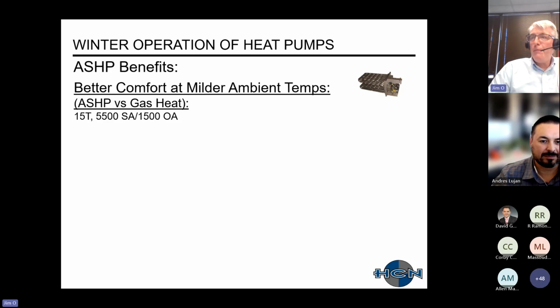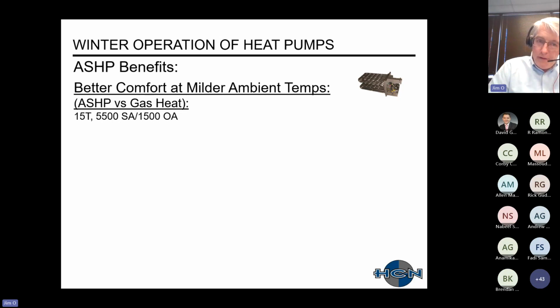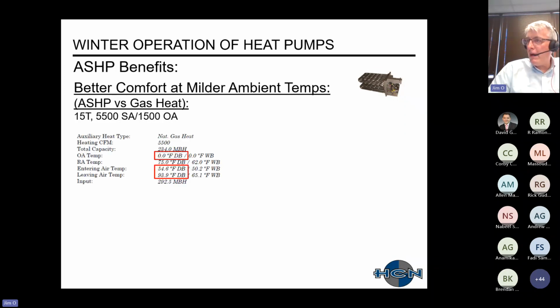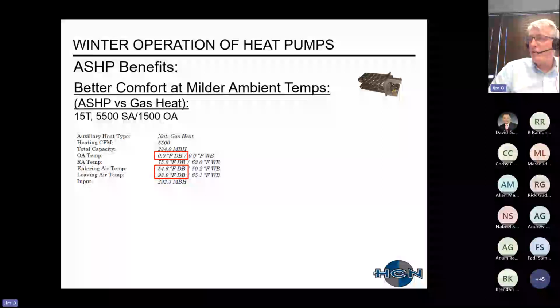Also, with air source heat pumps, the other benefit is that you'll have better comfort of your space at milder ambient temperatures. This is once again comparing an air source heat pump with a gas heat. There's my tonnage in the unit. This is what I came up with as a design of my heating system. Outside air temp of 0, maybe my return air temp should have been 70, 57 instead, maybe, of those room conditions. Mixed air temperature of 54. Therefore, my gas heating system is about a 40-degree rise.